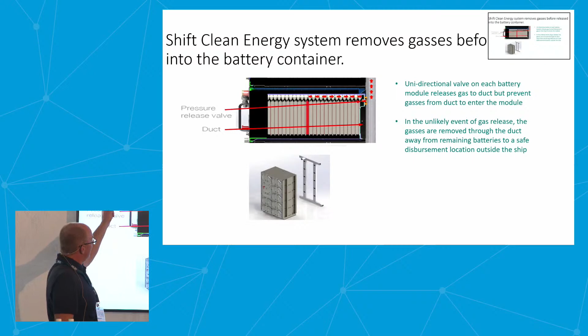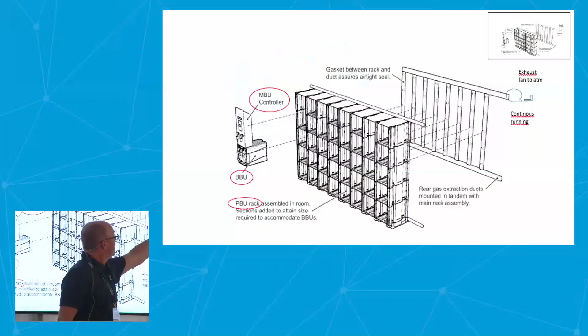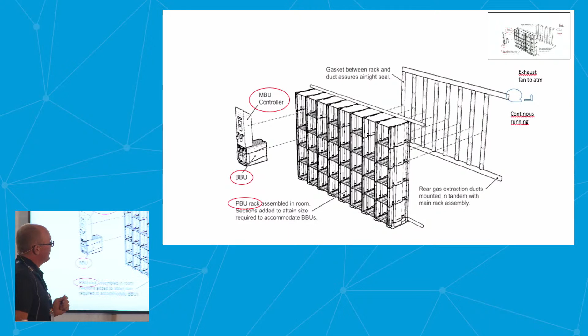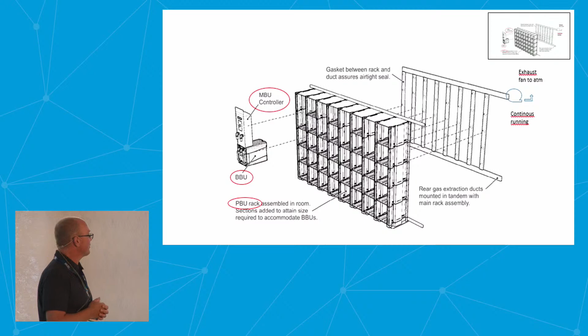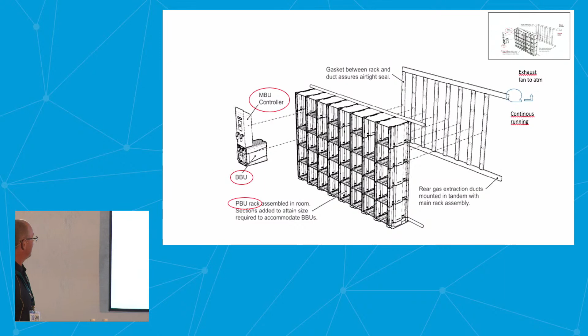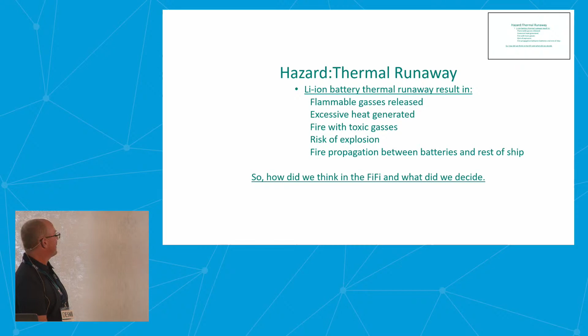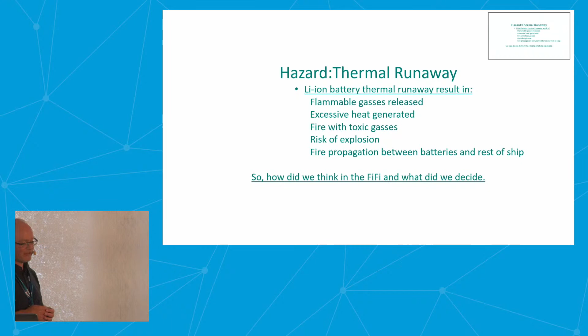And inside or behind the racks, this ventilation, one of the speakers before said much about the ventilation, is very important. And you have an exhaust fan that is continuously running, in case there is a thermal runaway and flammable or explosive gases are produced. They will then be released out to the atmosphere. And yeah, as I said, excessive heat, fire with toxic gases, and risk of explosion. So that's all the risks that we have identified with the installation.